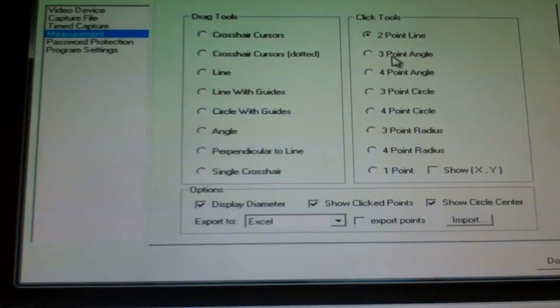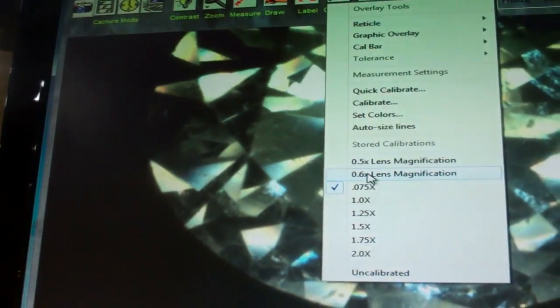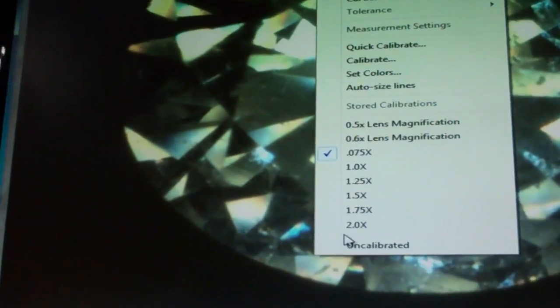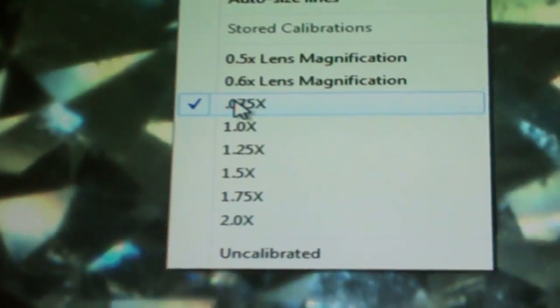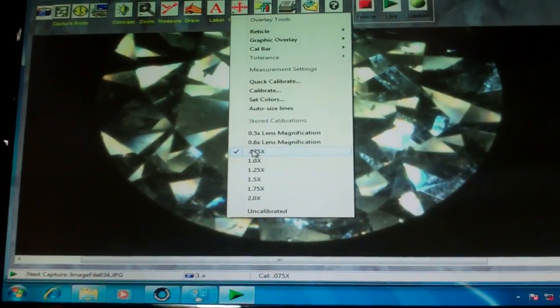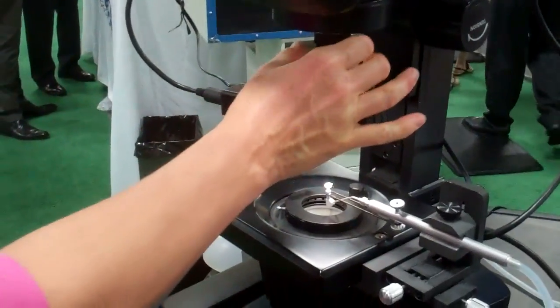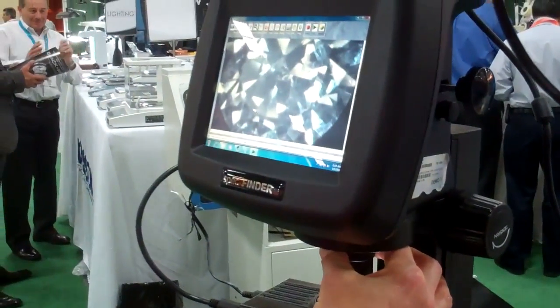Two-point line measurements, three-point angles, three-point circles — I'll show you that in just a second. In addition to that, we've got a variable zoom lens with preset calibrations, so that if you zoom in on a stone, you'll be able to calibrate your system. It has eight specific presets so you don't have to individually keep recalibrating for your measurements. This lens is an Edmund Optics lens — we call it our V1 — and it has a magnification from 10 to 55. Having that ability, we can zoom down into a stone with the ease of just a refocus, and the simple XY positioning system allows you to make fine-tuned movements with just the turn of a knob.